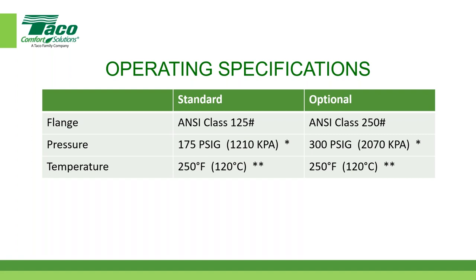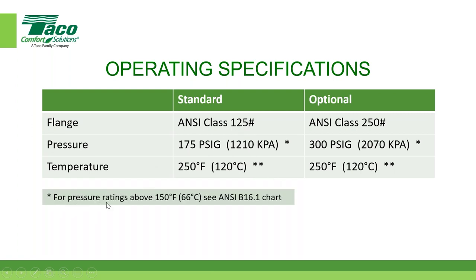And I'll get into why there are stars there in a second. Temperature ratings: standard, they're both 250, or optional, although we have seen higher applications, but consult the factory just to make sure. For the pressure rating above 150 degrees, you actually have to see this ANSI B16.1 chart. I didn't put it in here because it's tough to read, but it is in our documentation. After 150 degrees, the pressure rating of the pump casing goes down a little bit, not that much. I think you may lose 10% all the way up to 220 or so, but you can look at that chart. So for the most part, it shouldn't affect your design. And I'm pretty sure this is common for all of us pump manufacturers.